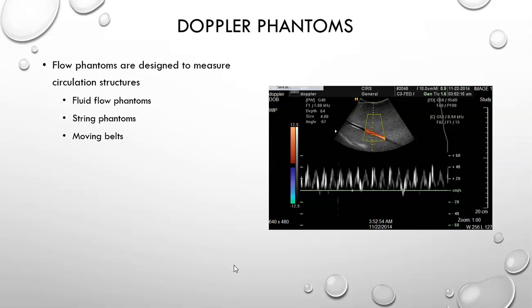The flow phantoms generally are used to measure the circulation. There's three types. There's fluid flow phantoms, string phantoms, and moving belts. Of these, it is a well-known artifact that string phantoms cause blooming artifact when used, or color bleeding artifact.